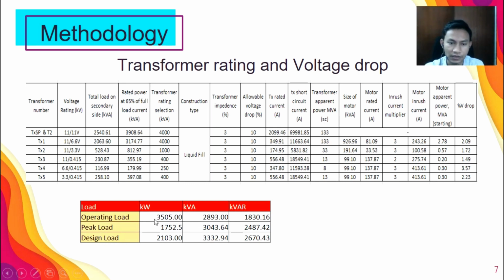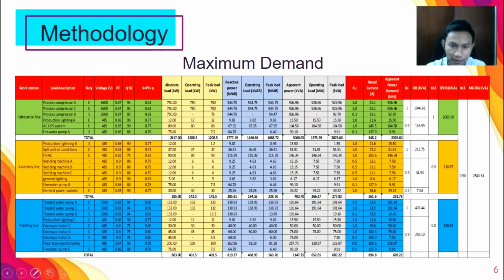For the operating load, we get 3505 kilowatts. For peak load, it is 1752. For design load, it is 2103. For the kVA, operating load is 2893, peak load is 3043, and design load is 3332. For the kVAR, operating load is 1830, peak load is 2487, and design load is 2670. We get these values from the maximum demand here. Below here, we can get the values of the operating load, design load and peak load.